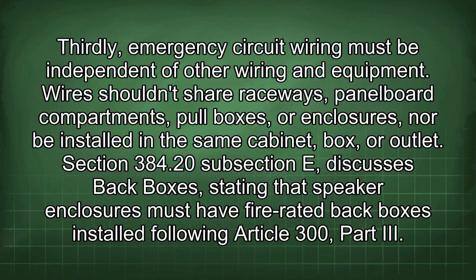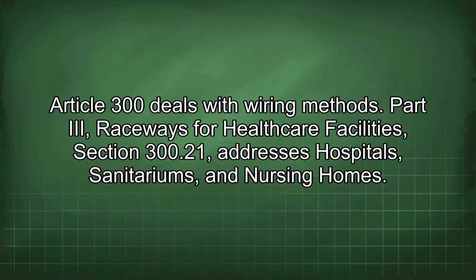Thirdly, emergency circuit wiring must be independent of other wiring and equipment. Wires shouldn't share raceways, panel board compartments, pull boxes, or enclosures, nor be installed in the same cabinet, box, or outlet. Section 384.20 subsection E discusses back boxes, stating that speaker enclosures must have fire-rated back boxes installed following Article 300, Part Roman 3. Article 300 deals with wiring methods.